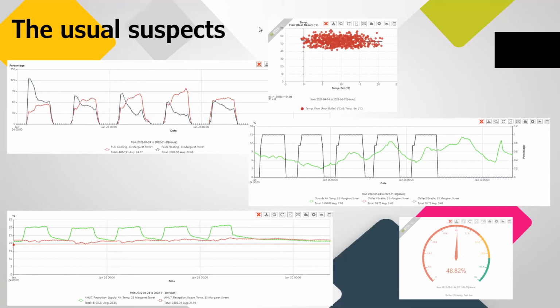Simultaneous heating and cooling in the same place. Because a wrong temperature setting was applied to a specific area, the heating, ventilation and air conditioning system was fighting within itself to maintain that very tight temperature, therefore having units cooling and other units heating the same place at the same time. Temperature overshooting. Instead of providing a suitable air temperature in a specific place, the system was probably overridden to increase that temperature, probably due to a complaint from occupants. It was never reverted to normal operation.